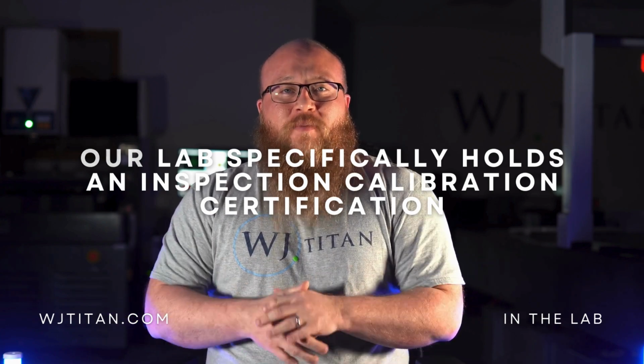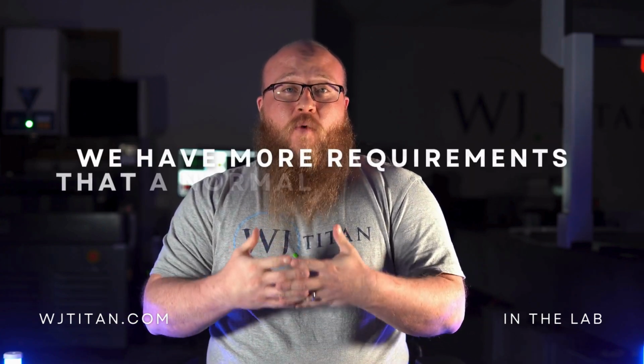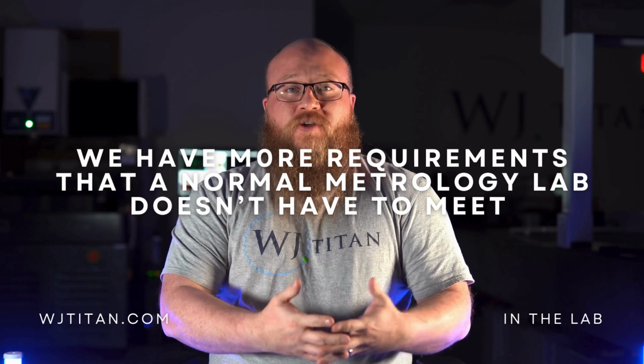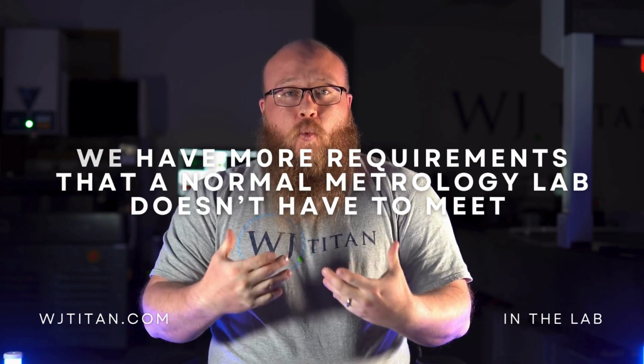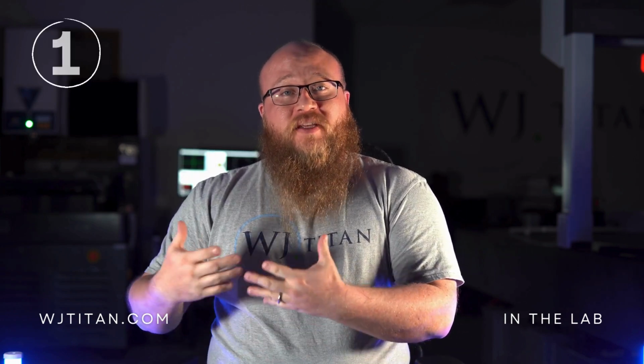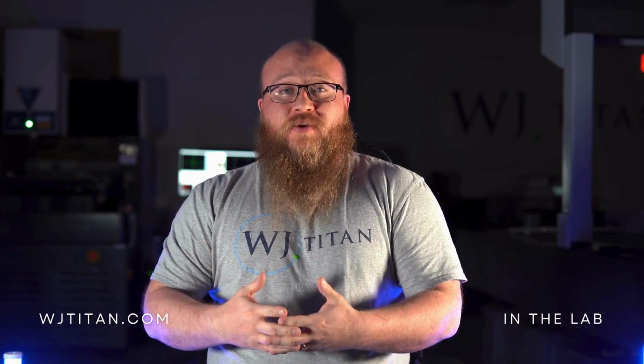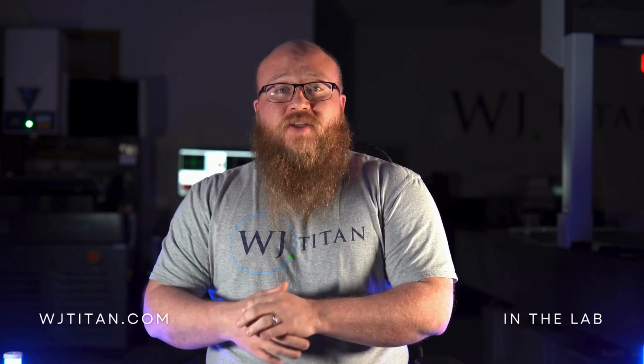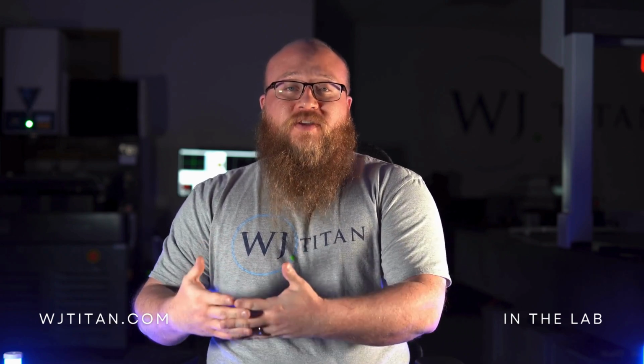So what that means for a lab like us is we have more requirements that a normal metrology lab doesn't have to meet. We're required to guarantee that our equipment stays calibrated in between its annual calibration process by doing what we call monthly cross-checks. It's where we verify that our machines are still performing to hold their standard of requirement.